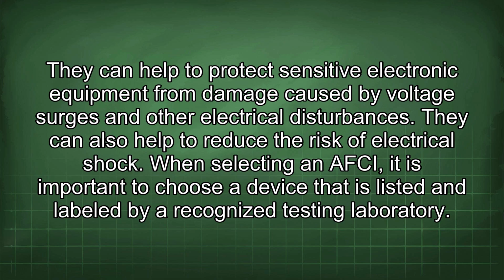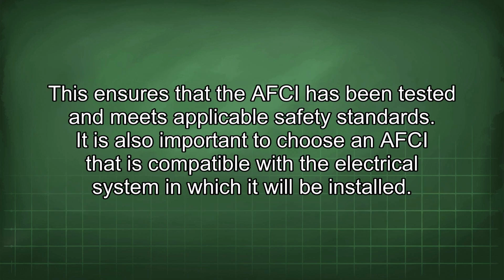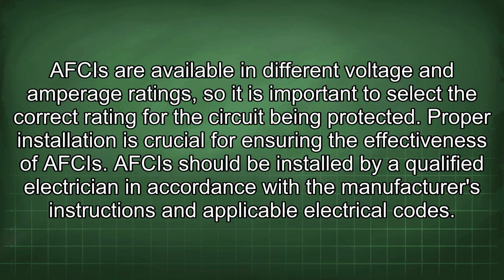When selecting an AFCI, it is important to choose a device that is listed and labeled by a recognized testing laboratory. This ensures that the AFCI has been tested and meets applicable safety standards. It is also important to choose an AFCI that is compatible with the electrical system in which it will be installed. AFCIs are available in different voltage and amperage ratings, so it is important to select the correct rating for the circuit being protected. Proper installation is crucial for ensuring the effectiveness of AFCIs.